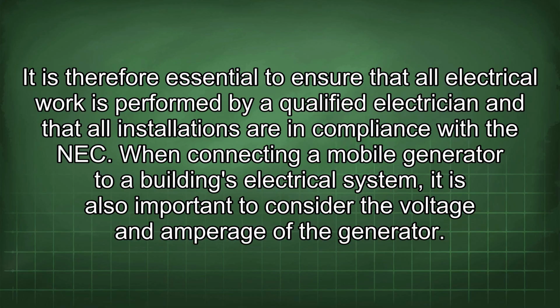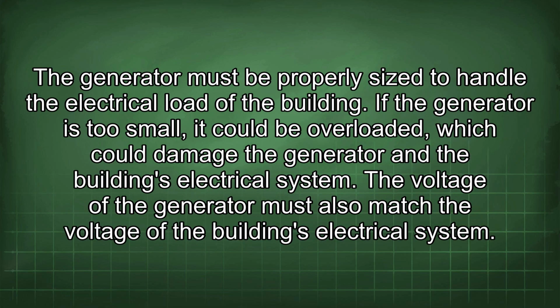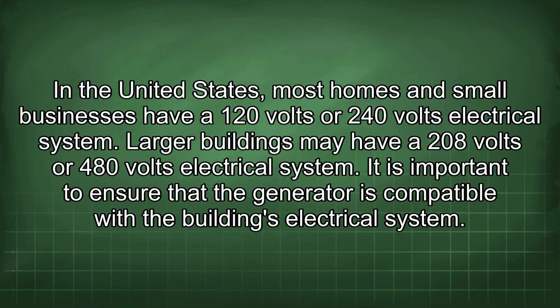When connecting a mobile generator to a building's electrical system, it is also important to consider the voltage and amperage of the generator. The generator must be properly sized to handle the electrical load of the building. If the generator is too small, it could be overloaded, which could damage the generator and the building's electrical system. The voltage of the generator must also match the voltage of the building's electrical system. In the United States, most homes and small businesses have a 120 volt or 240 volt electrical system. Larger buildings may have a 208 volt or 480 volt electrical system. It is important to ensure that the generator is compatible with the building's electrical system.